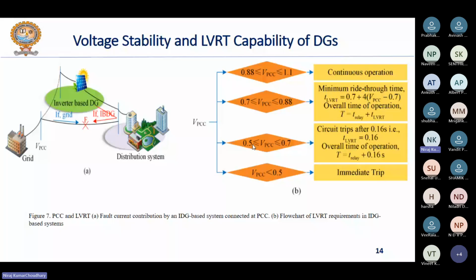from the system. Because whenever there is an isolation of any power source from the system, then what is the problem? Ultimately, your load demand may not be fulfilled if the power sources are disconnected from the system, right? So during faults also, DG must remain connected to the grid, microgrid you can say, for a specific time, right? So this time duration basically depends upon the magnitude of the PCC bus, right? So here in this figure A, you can see this is the PCC bus, means the point of interface of the utility grid and the microgrid system.